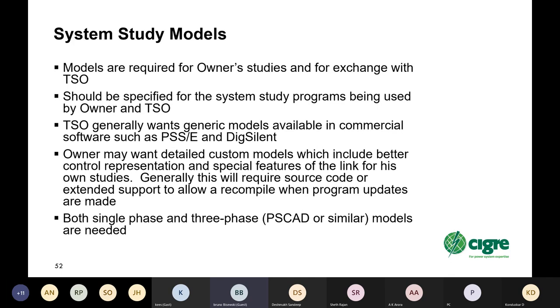However, the owner may want detailed custom models which include better control representation and all the special features of the HVDC link for his own studies. This might require either the source code or at least full documentation, including block diagrams of all of the functions that are included in the controllers. And usually both single phase models for PSS/E and DigSilent type programs, and three phase models for programs like PSCAD or EMTP, EMTP-RV or similar are needed.